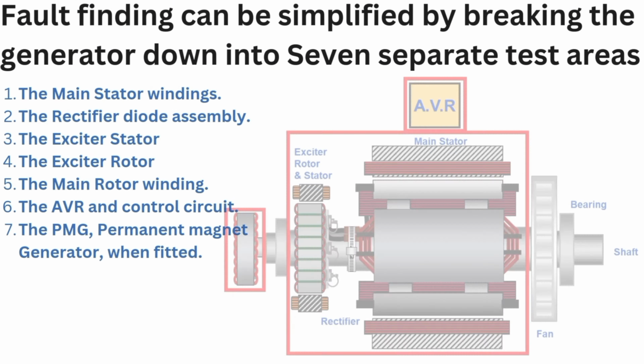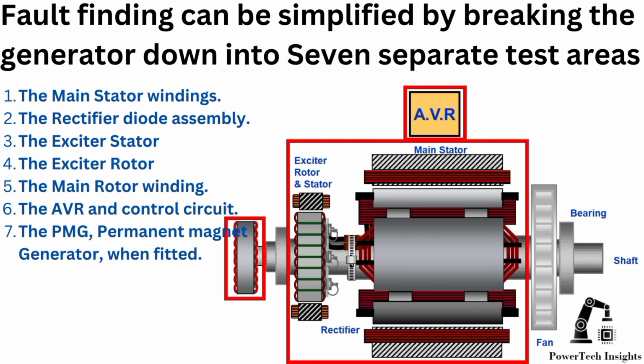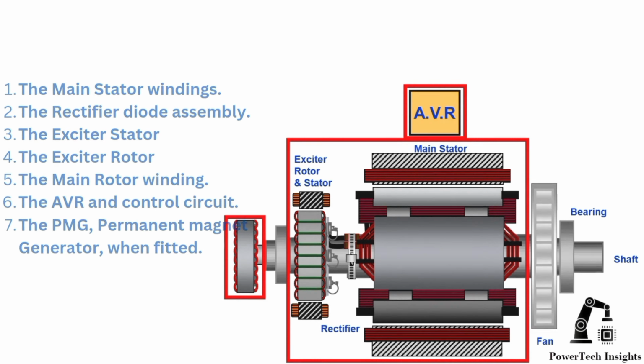The fault finding and troubleshooting of three-phase AC generator alternator. Fault finding can be simplified by breaking the generator down into 7 separate test areas. 1. The main stator windings. 2. The rectifier diode assembly. 3. The exciter stator. 4. The exciter rotor. 5. The main rotor winding. 6. The AVR and control circuit. 7. The PMG, permanent magnet generator, if fitted.